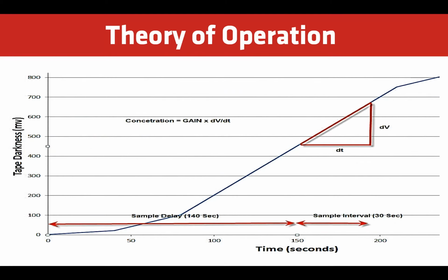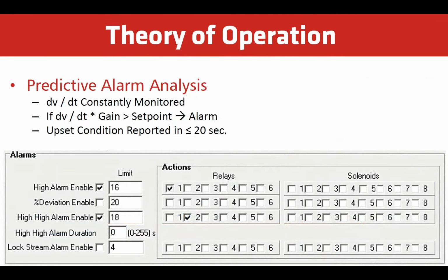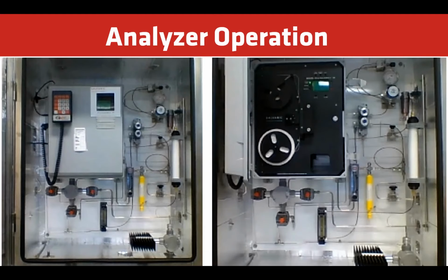A pulse counter is used to maximize tape life by reducing the space between each analysis stain. The analyzer software includes a predictive alarm. Even though the analysis sequence is 3 minutes, this will alert the DCS of any issues in less than 30 seconds. Galvanic's ProTech Nano 3 is our 3rd generation tape analyzer, marking 30 years of field experience.